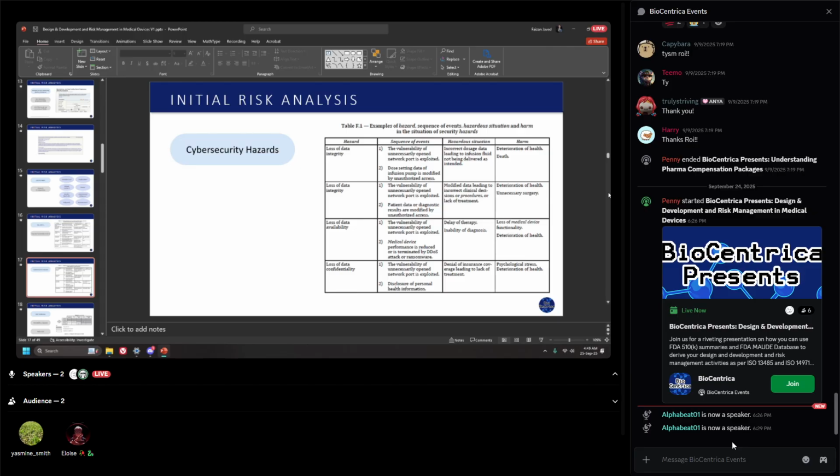And not only are you giving them the evidence that your device is safe, through penetration testing and some other test methods as well, you also have to share your protocols, processes, and procedures regarding how you conduct cybersecurity risk analysis, and how you make sure that once it's out in the market, you are tracking it and making sure your device is safe from vulnerabilities that come later.